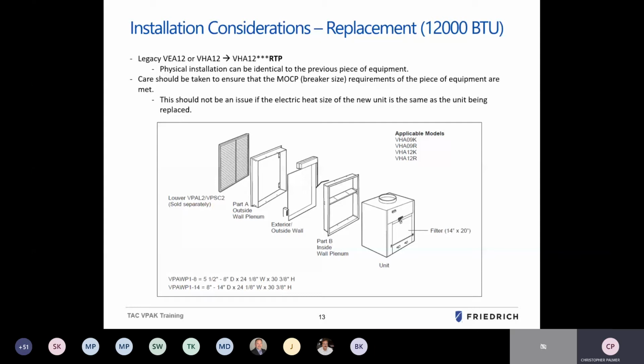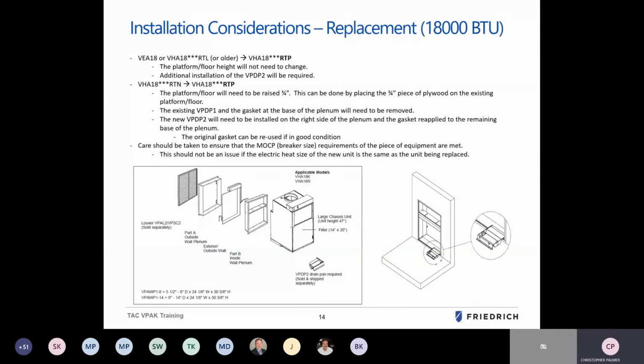VEA-12 or VHA-12, converting to a VHA-12 RTP. Once again, same recommendations, making sure that your breaker sizes are appropriate and that your wire size is appropriate based on the heater size. The VHA-18 and the VEA-18 RTP, the platform height will not need to change.